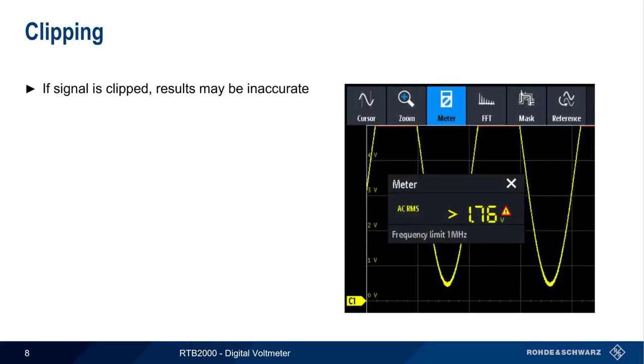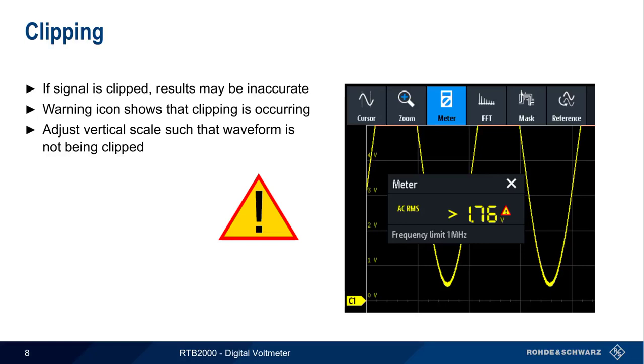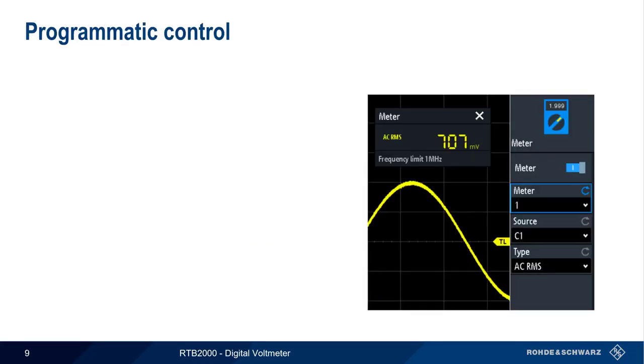One important thing to remember is that if the signal is being clipped—that is, if some portion of the waveform extends beyond the limits of the display—the DVM measurement results may be inaccurate. When this occurs, the RTB will display a small warning icon next to the measurement. In this case, the vertical scaling of the oscilloscope should be adjusted so that no part of the waveform is being clipped.